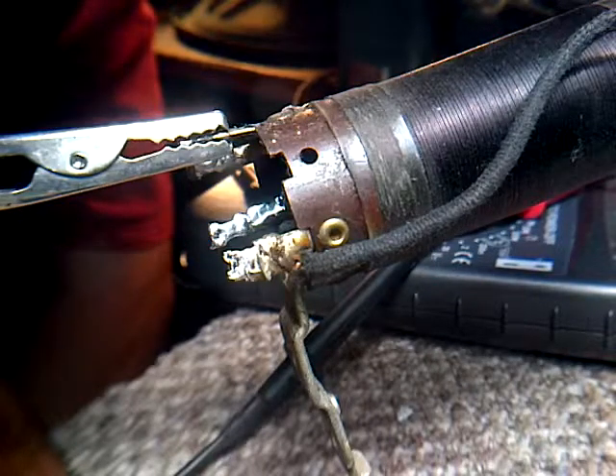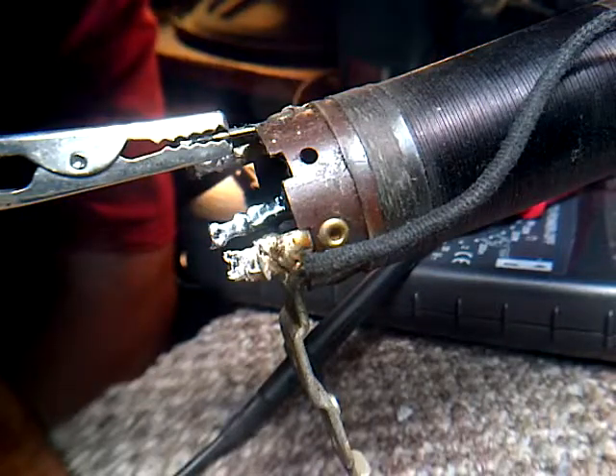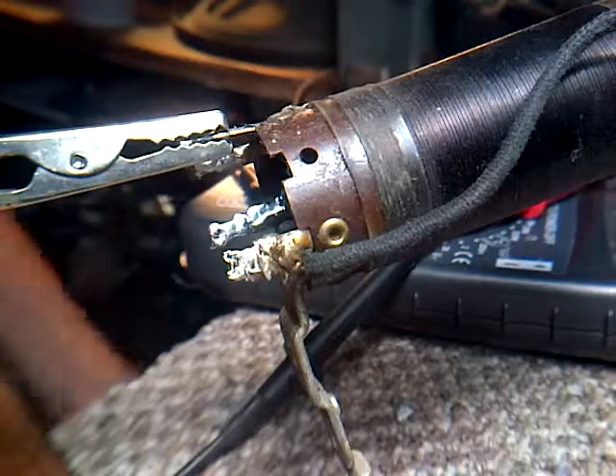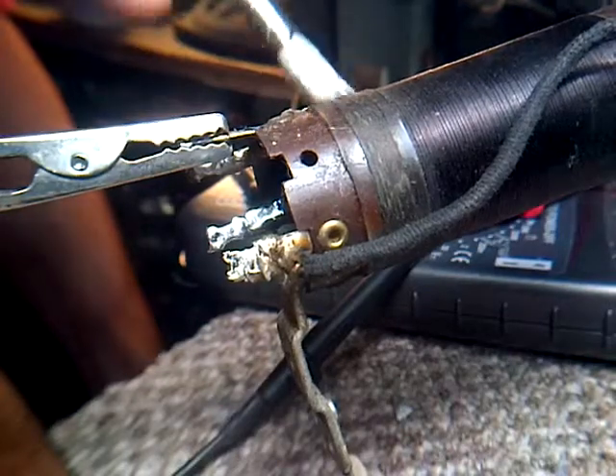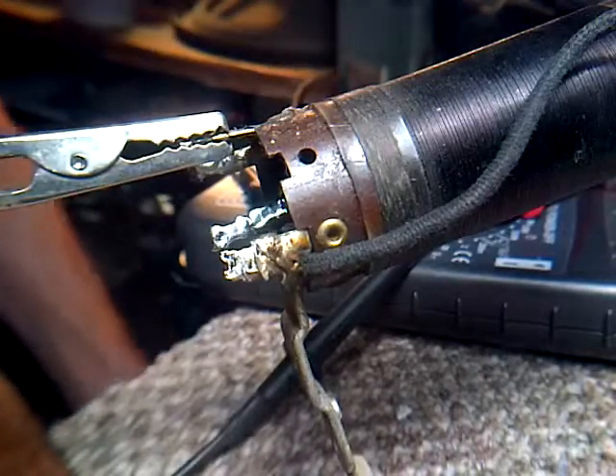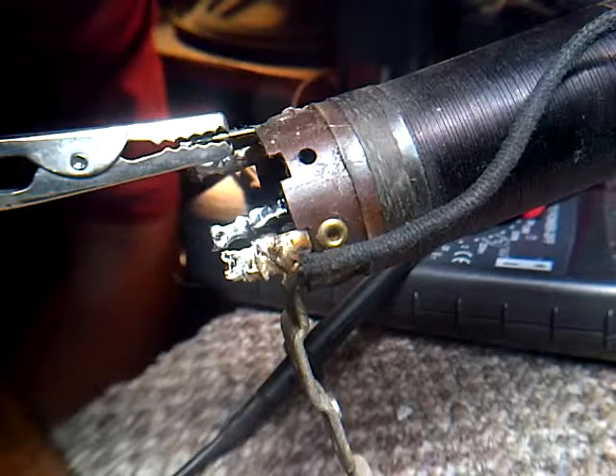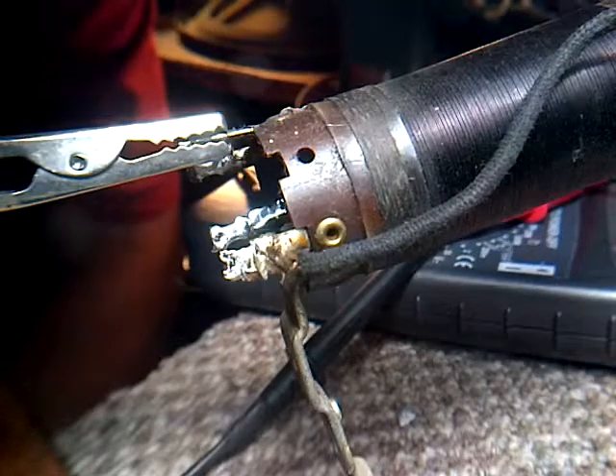Another possibility is to try to bare off the outside turns a little bit, contact them with my meter, and at that point I'm beyond these connections and right in the coil. This coil does not look good. I'm just using a dry brush at this point. Sorry you can't see exactly what I'm up to here, but it doesn't look too good in here.